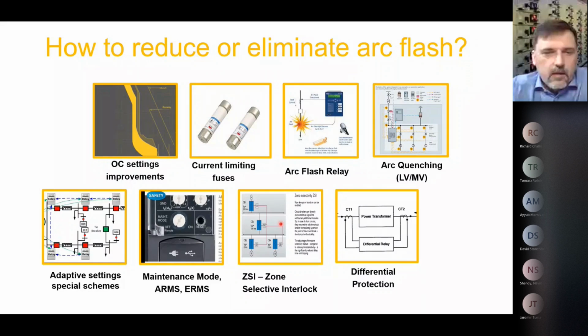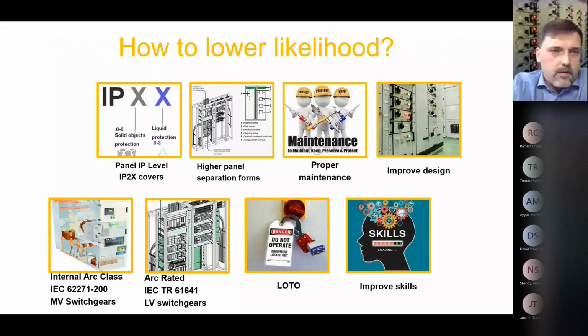Very similar concept. Differential protection, very fast, but requires some attention when we try to use it for arc flash, because it will not detect everything, but it's nice to have. We can also lower the likelihood of arc flash to happen. And if I go step by step, I should say that improved skills and proper maintenance are the most common, and lockout tagout. But let's go step by step.